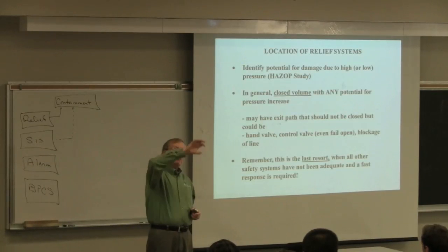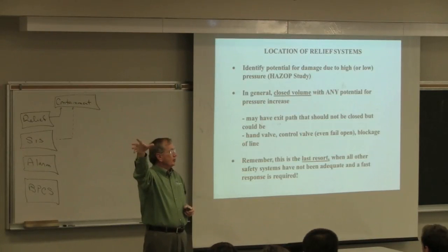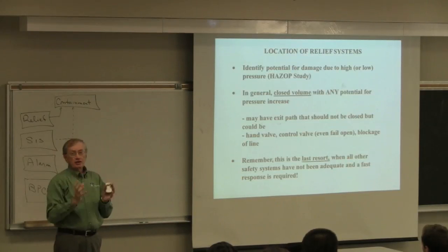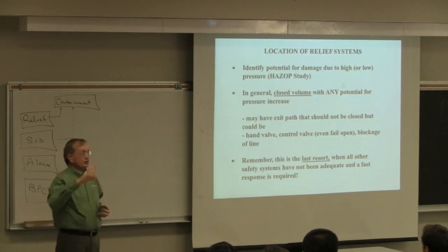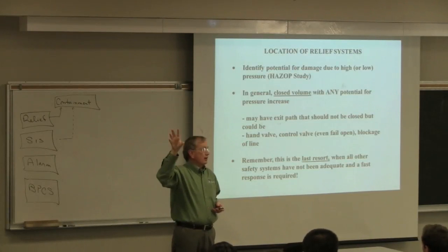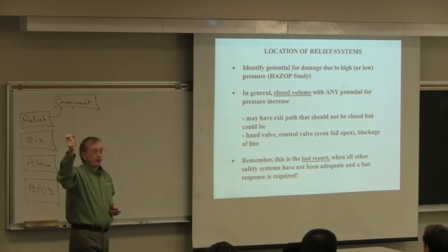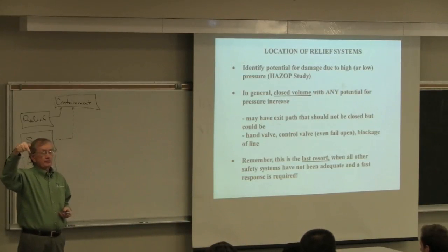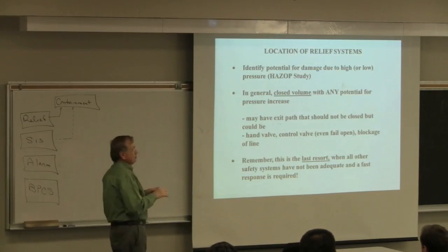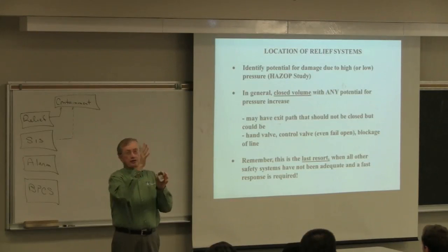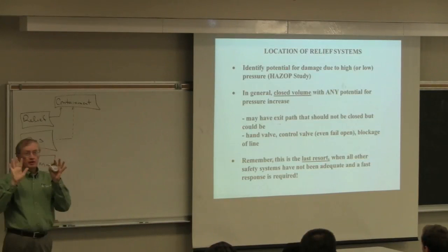If there's a pipe coming out of a vessel and there's a valve, even with a big sign saying 'don't close this valve,' that sign doesn't count—somebody can close it. Even a fail-open control valve doesn't exempt the vessel, because the control system can fail. The only exception is if two vessels are connected by a large-diameter pipe with no restrictions—then you can put pressure relief on one and not the other. If there's any potential restriction in that pipe, you must put pressure relief on both vessels.